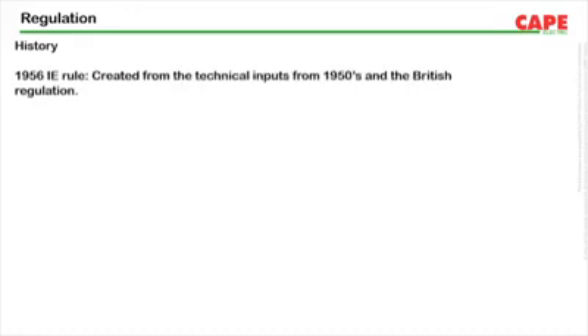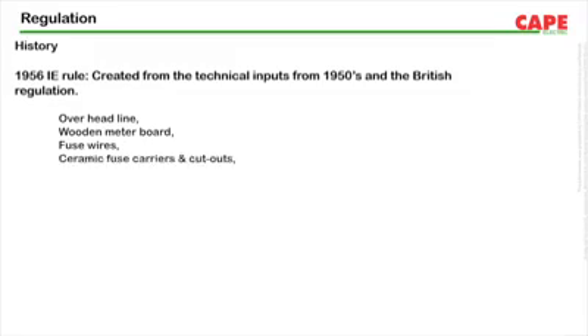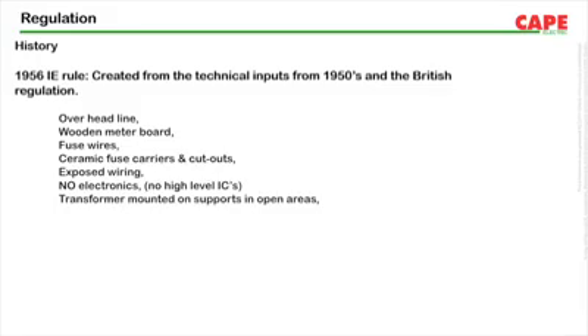If you look at the history of the part of CEA regulation which explains electrical safety up to 650 volts, it's basically from the 1956 IE rule. And this 1956 IE rule was created based on the technical inputs from the previous British regulation. What we should remember is that during 1956, electricity supply was quite different from today. Meter boards and cutout fuses were fixed in wood. Fuse wires and ceramic fuse carriers were used, with exposed wiring.